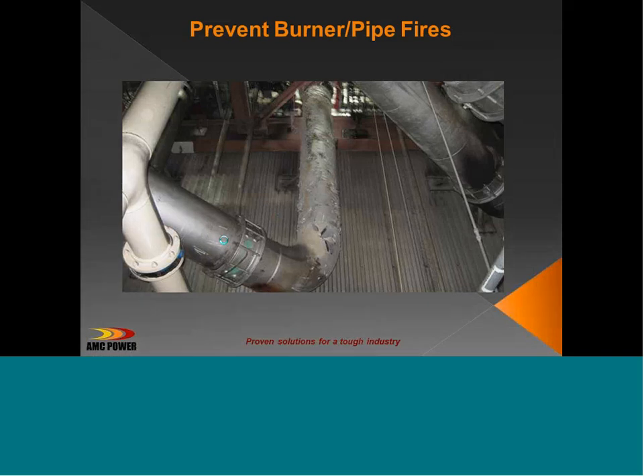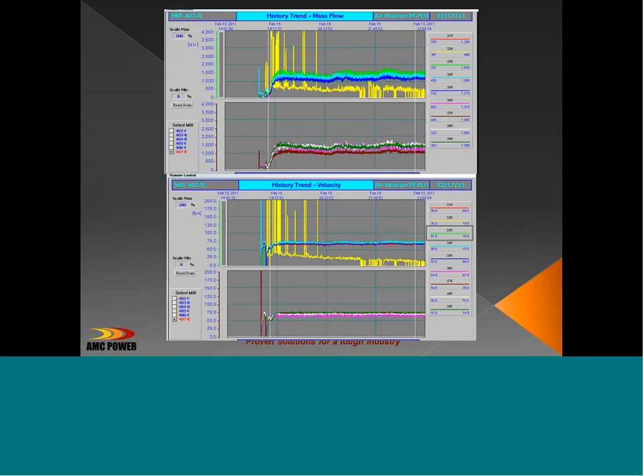If we look at the data from this, this particular plant has the option to have what's called a PA kicker. A PA kicker means they're continuously monitoring coal mass and coal speed. If coal velocity in any pipe gets below a set point, the primary air is automatically increased to try to prevent layout. That feature was not turned on in this particular power plant, and we can see what happened. When this mill was brought back into service, there was a slug of coal that went to the pipe that had a fire.